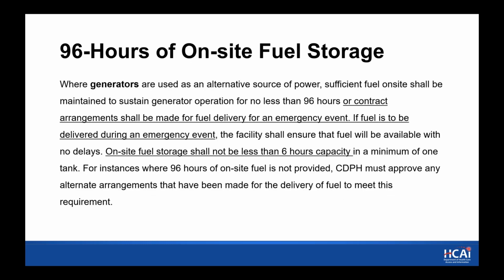So I wanted to talk about the 96 hours of on-site fuel. A lot of this language is directly from the law, so I'm just going over it here with you. It states that when generators are used as an alternate source of power, sufficient fuel on site shall be maintained to sustain operation for no less than 96 hours, or contract arrangements shall be made for fuel delivery for an emergency event. The law specifically states, if fuel is to be delivered during an emergency event, the facility shall ensure that fuel will be available without delays.